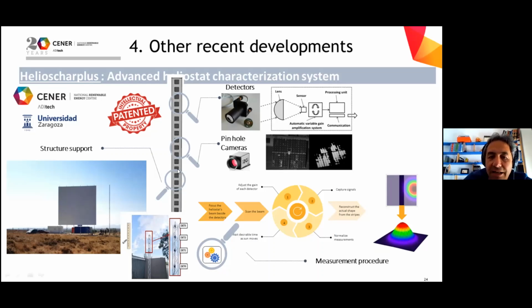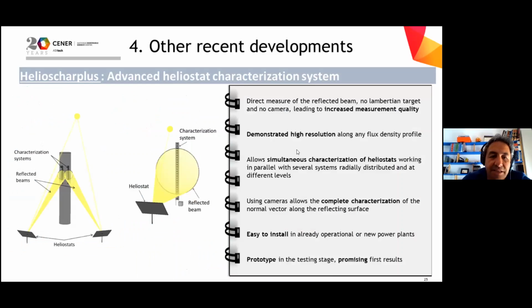The pole is fixed, and this pole scans the reflected image of the sun from the heliostat. The heliostat is also fixed. By scanning this image, we can reproduce the reflected image of the sun and also get all the measurements with very high accuracy. Another advantage of this system is that it can be easily installed during commissioning to test the quality of the heliostat, and also during operation. We can place this pole on the top of the tower, even at different heights, so we can run different systems in parallel, and we can check the optical quality of the heliostat not only at the beginning of the commissioning, but also during the whole life of the plant.